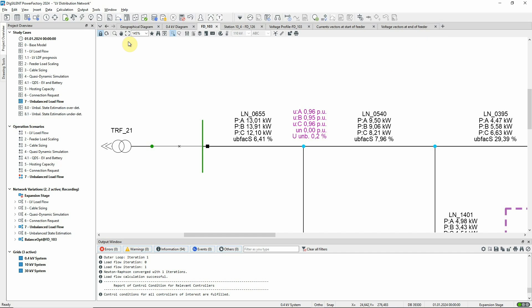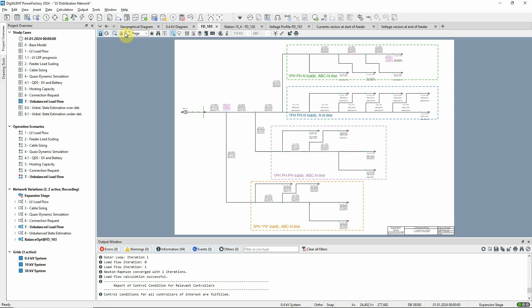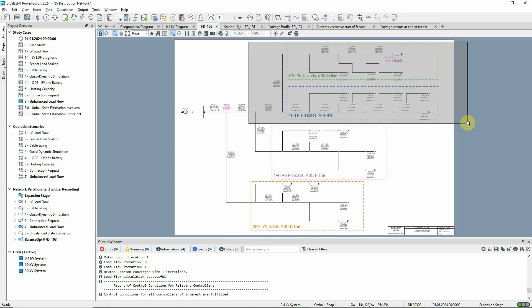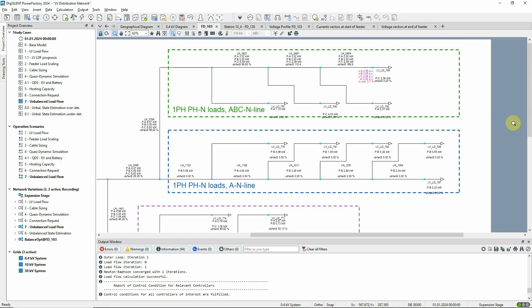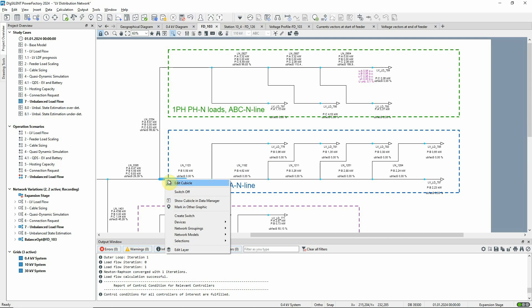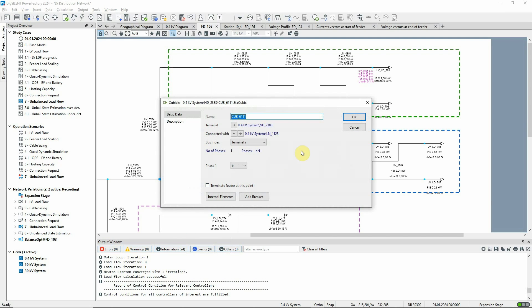Let's now look at the changes made to the network elements by the phase balance optimisation. In the first branch, the single phase loads have been distributed between the phases. In the second branch, all the single phase loads are connected to a single phase line, so they couldn't be redistributed. However, the single phase line has been reconnected from phase A to phase B.